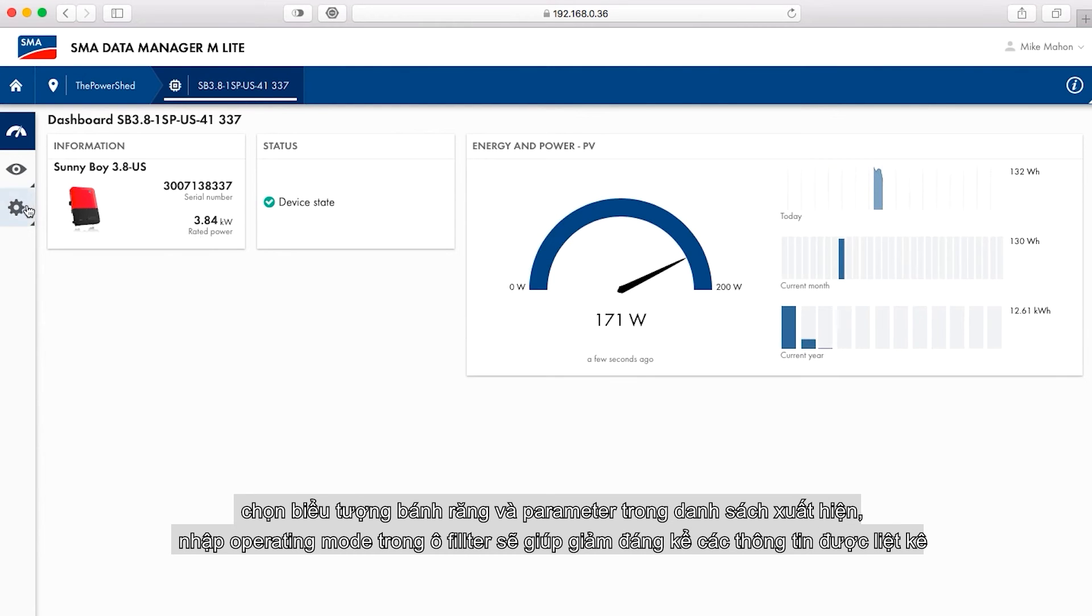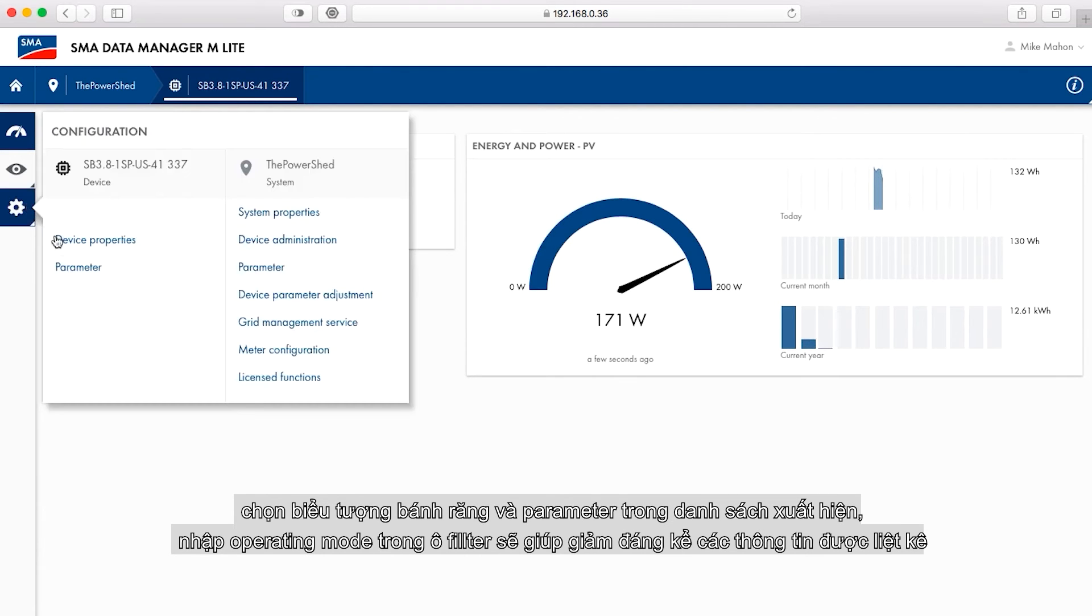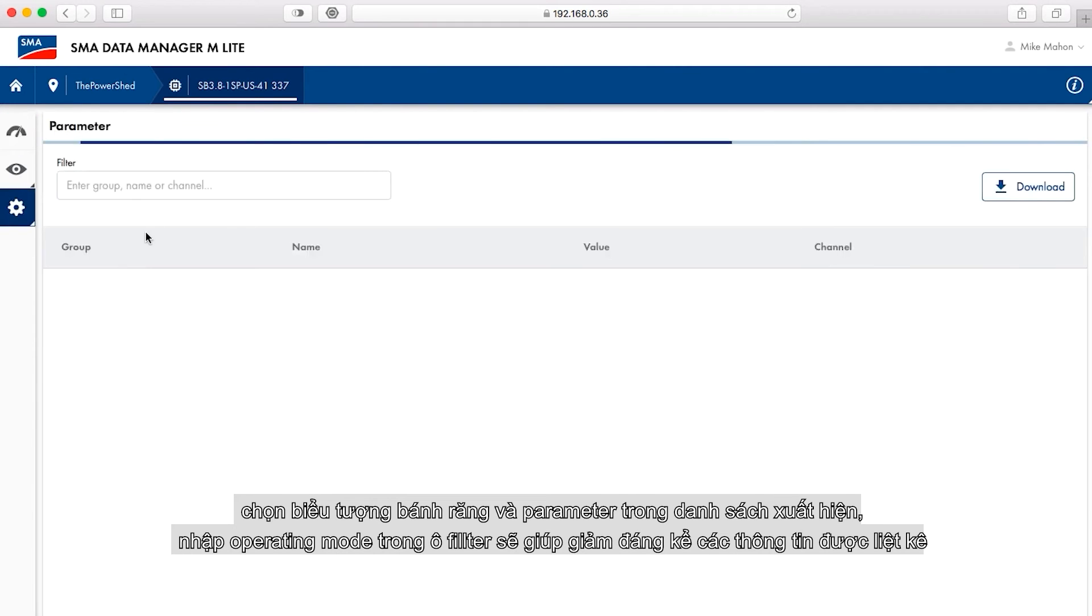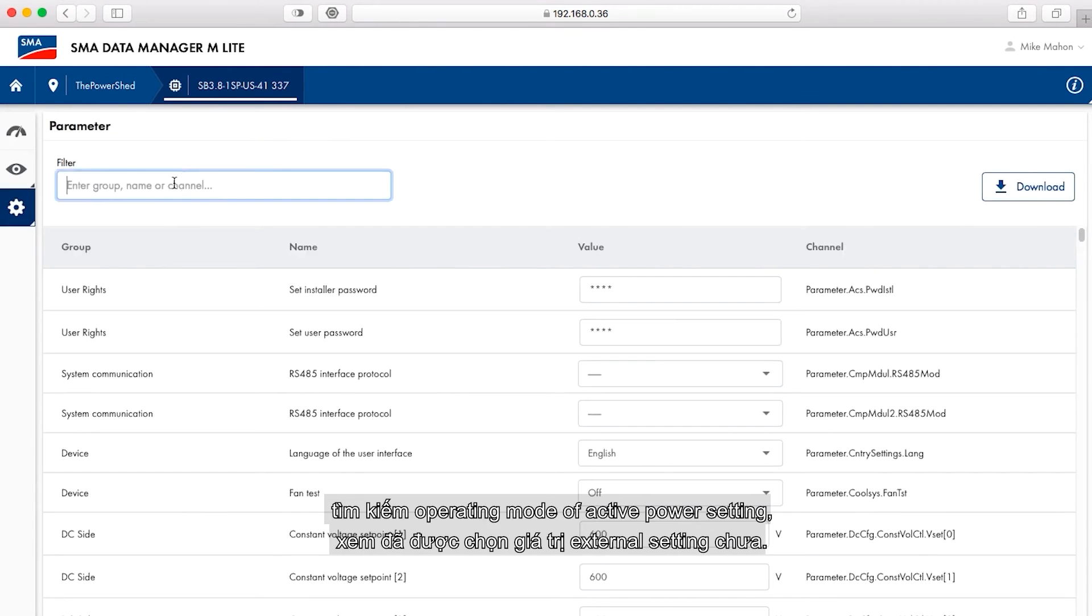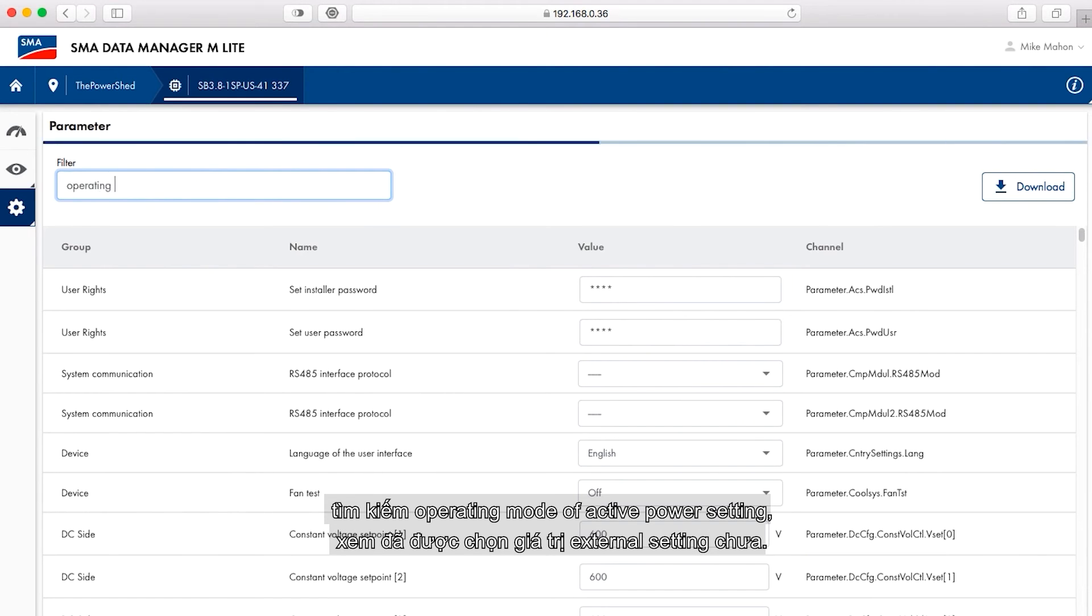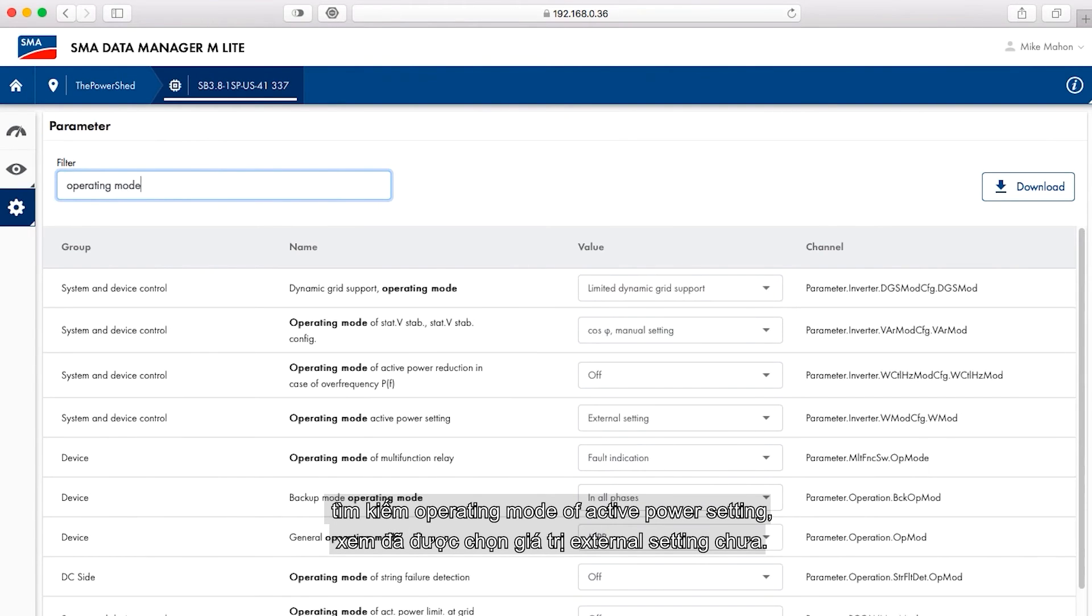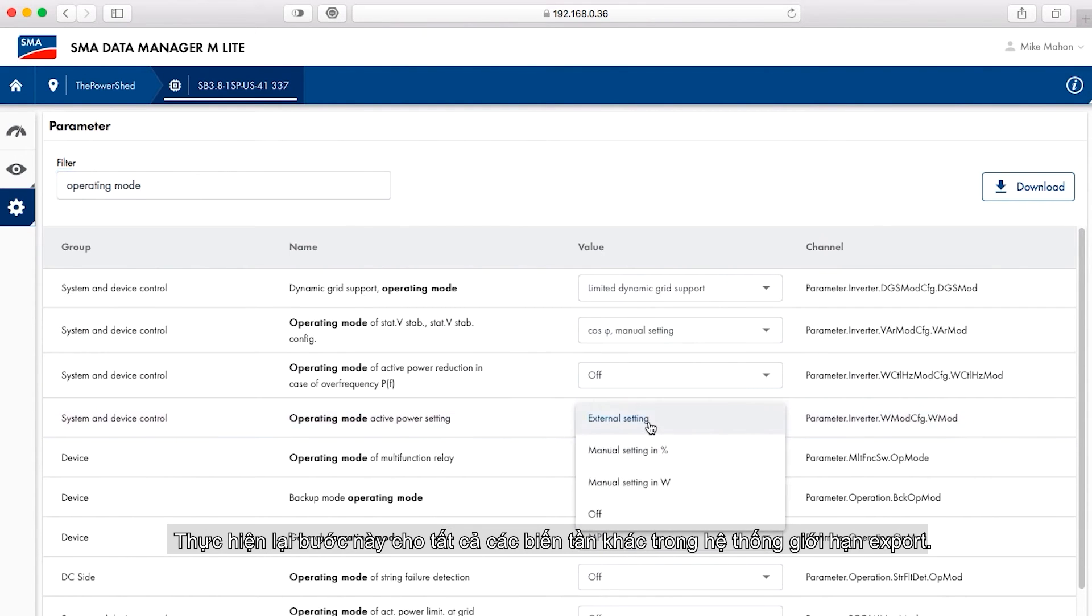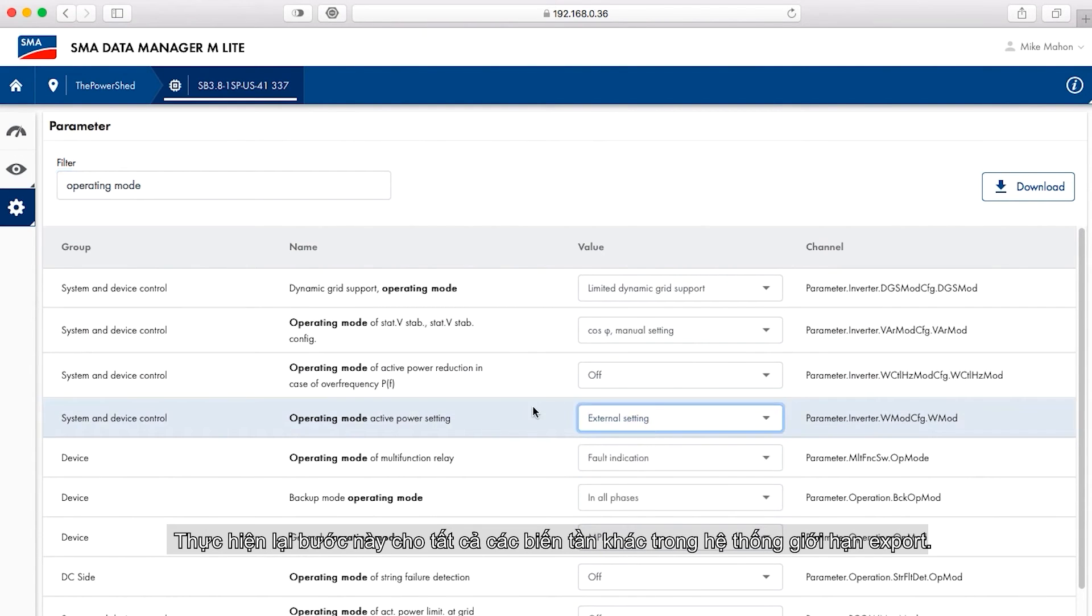Typing operating mode in the filter window will reduce the parameters listed dramatically. Verify that the operating mode of active power setting parameter has the external setting value selected. Repeat this step for all inverters participating in the export limitation.